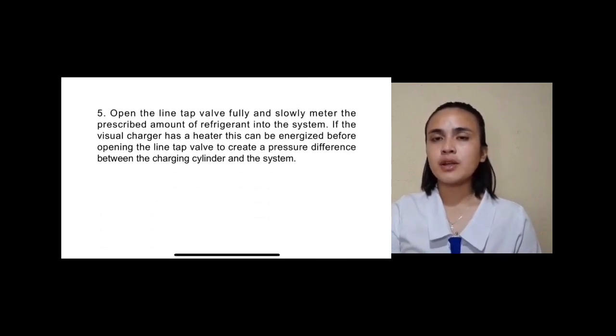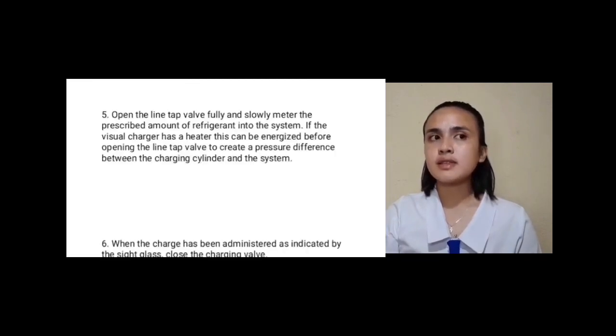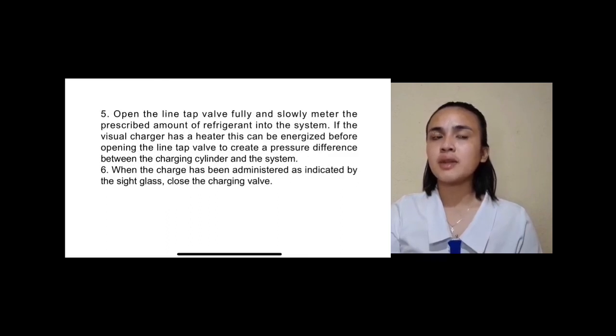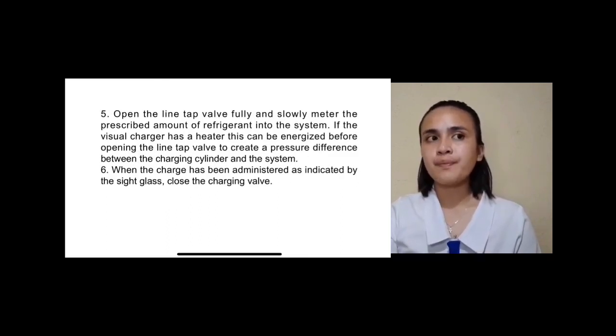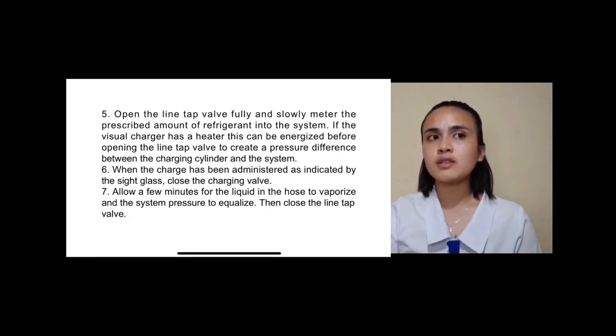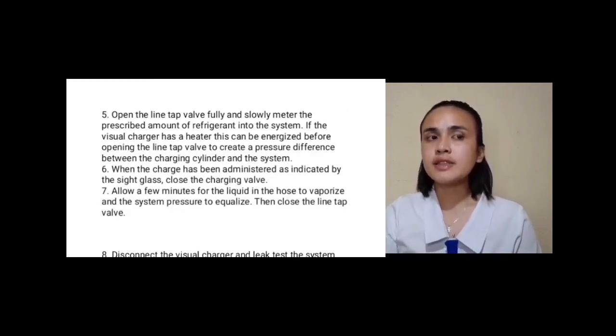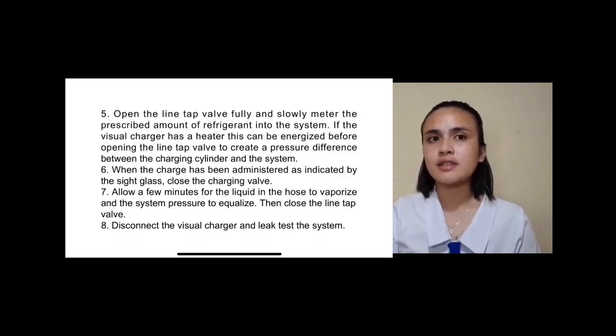Number 4. Note the level of the refrigerant in the sight glass. Number 5. Open the line tap valve fully and slowly meter the prescribed amount of refrigerant into the system. If the visual charger has a heater, this can be energized before opening the line tap valve to create a pressure difference between the charging cylinder and the system. 6. When the charge has been administered as indicated by the sight glass, close the charging valve. 7. Allow a few minutes for the liquid in the hose to vaporize and system pressure to equalize. Then close the line tap valve. And 8. Disconnect the visual charger and leak test the system.